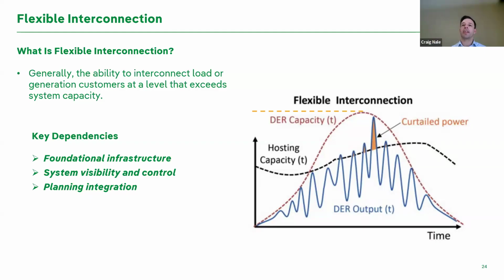With flexible interconnection, instead of either taking it offline or building to that peak, we're just going to curtail the power output from that DER during that small period of time. So typically, about 90% of the time it operates as if totally normal, but for a very short period we're going to curtail you and bring you back into compliance.